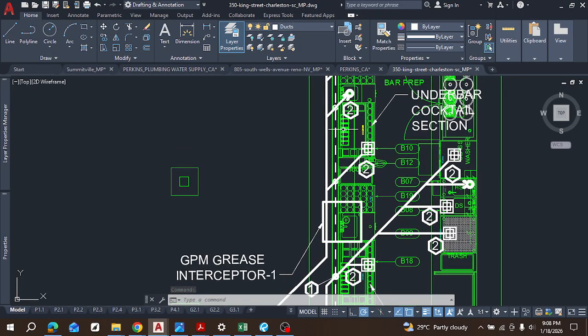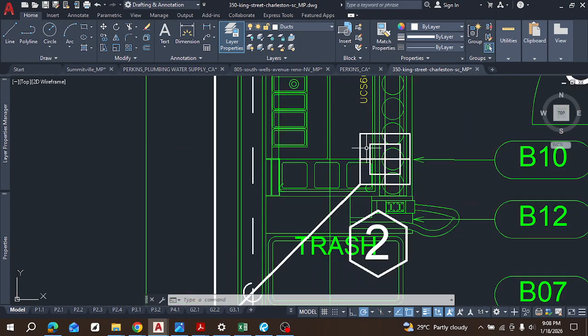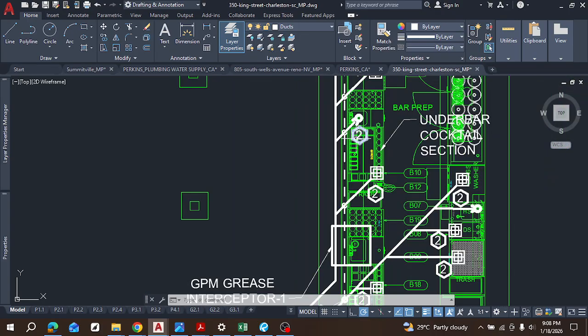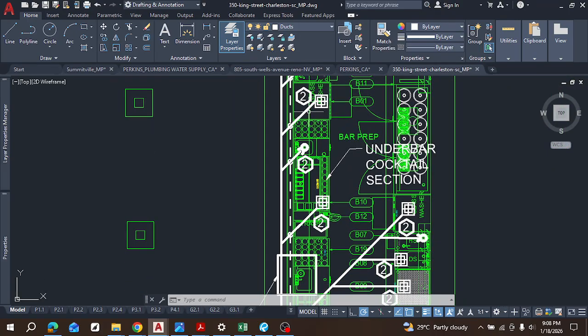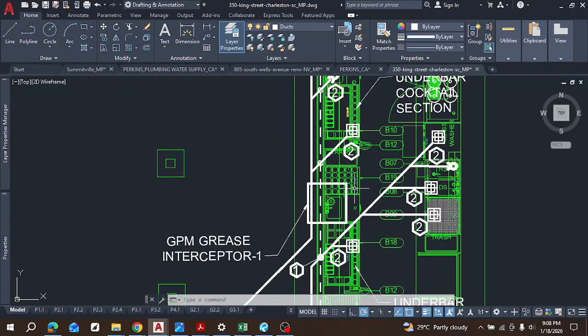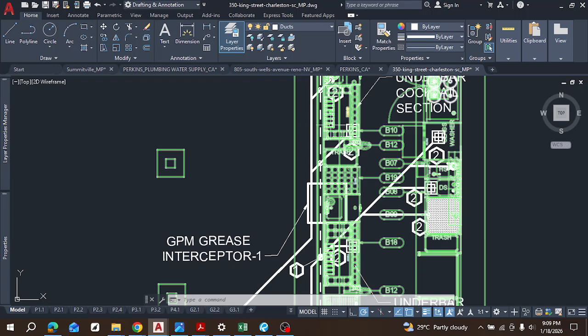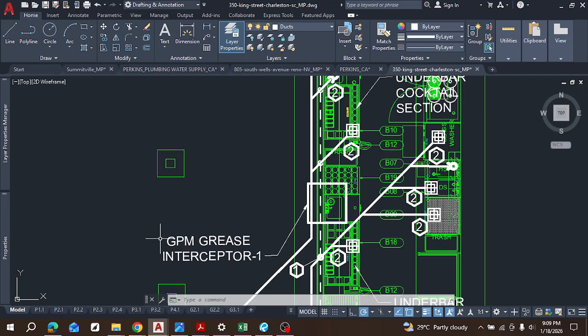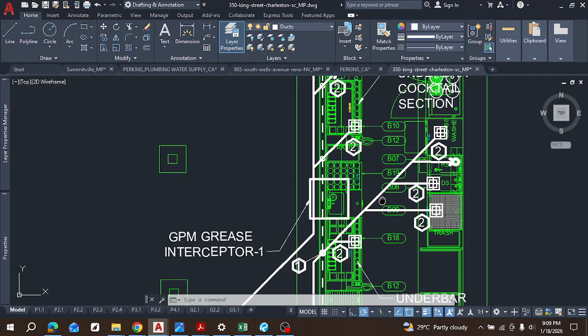Now this stands for floor sink, right? And this is the kitchen section. So you just see all these pipes coming in and then it enters into the Grease Interceptor. Now, based on the total GPM of all of them, multiplied by your 30 minutes or 1 hour, it will give you an idea of the size of Grease Interceptor you select, right? So this is just an example.